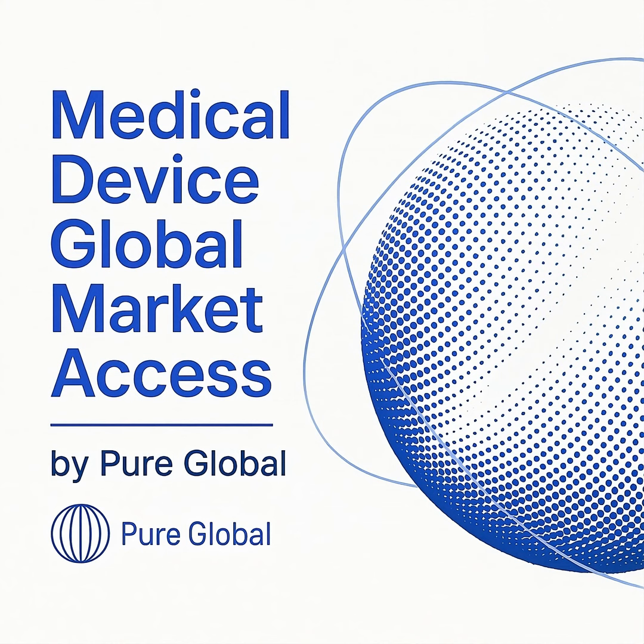A successful submission hinges on robust clinical evidence and a proactive risk management process. Your clinical evaluation report must be thorough, drawing from clinical investigations, literature reviews, and post-market surveillance data from similar devices. Likewise, your risk management file, compliant with ISO 14971, must document a comprehensive analysis of all potential risks throughout the device's lifecycle and the measures taken to mitigate them.